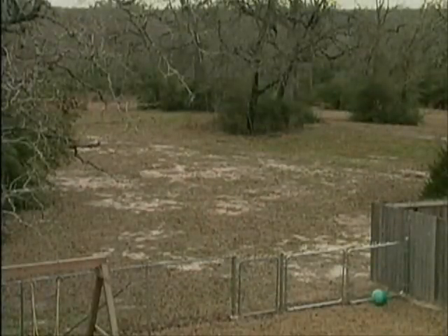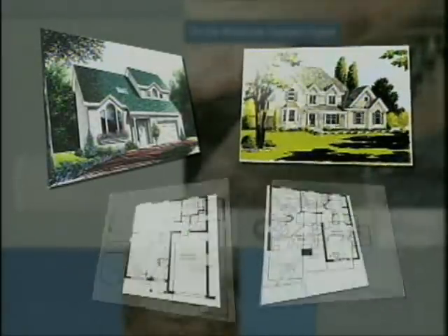The design process begins with an assessment of the site's treatment capability. Consideration must also be given to the expected use of the facility and the treatment needs of the watershed. The quantity of wastewater generated in a home is estimated from the number of bedrooms or the square footage of a residence. However, occupants and their activities can greatly affect the flow, quantity, and rate.